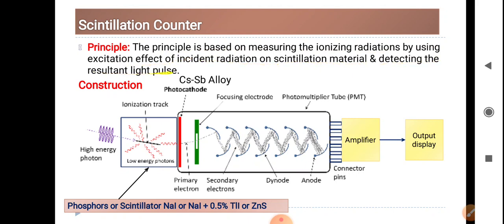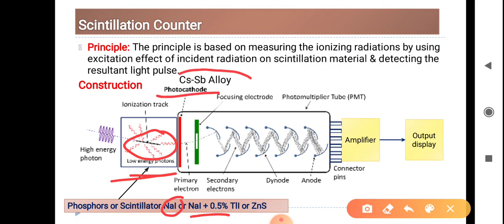Coming to the construction, it consists of a phosphor or scintillation chamber. This phosphor material is made up of sodium iodide, or sodium iodide with 0.5% thallium iodide, or zinc sulfide. It is connected with the photocathode, which is made up of cesium-antimony alloy.